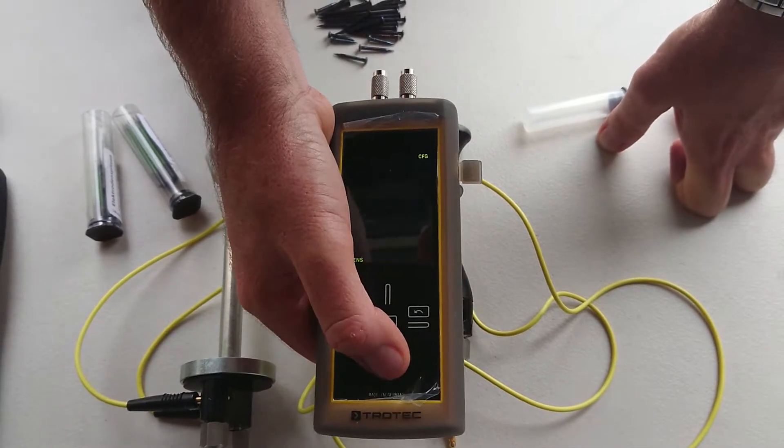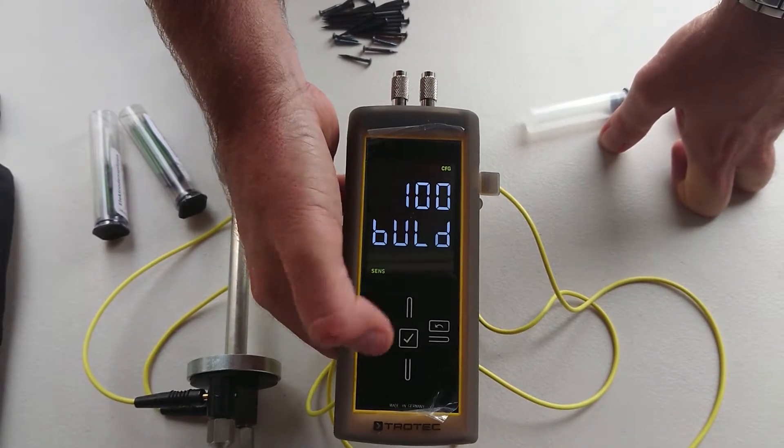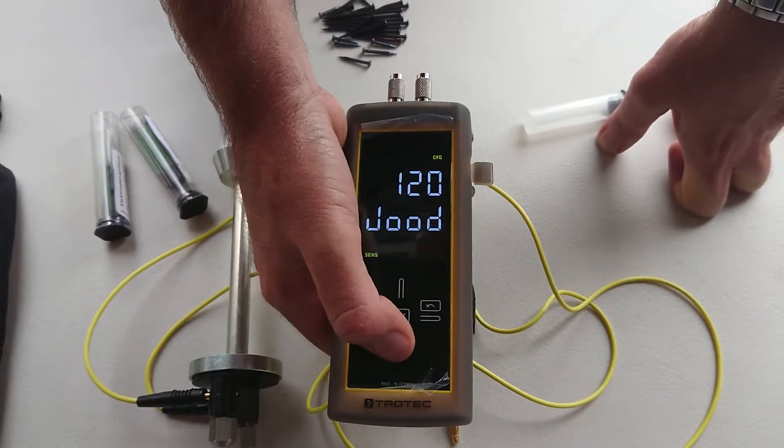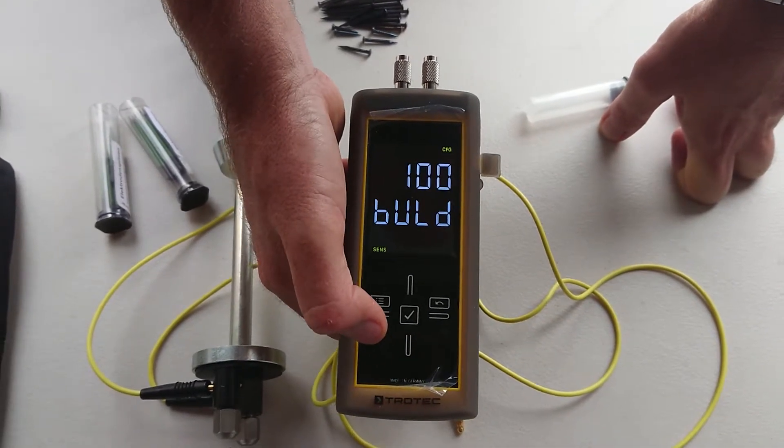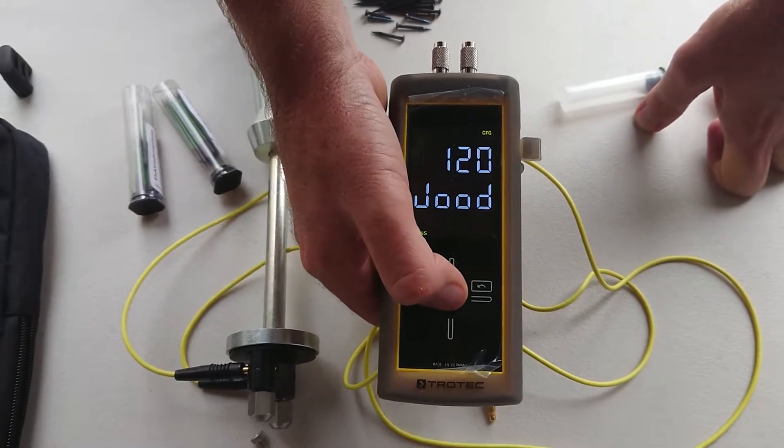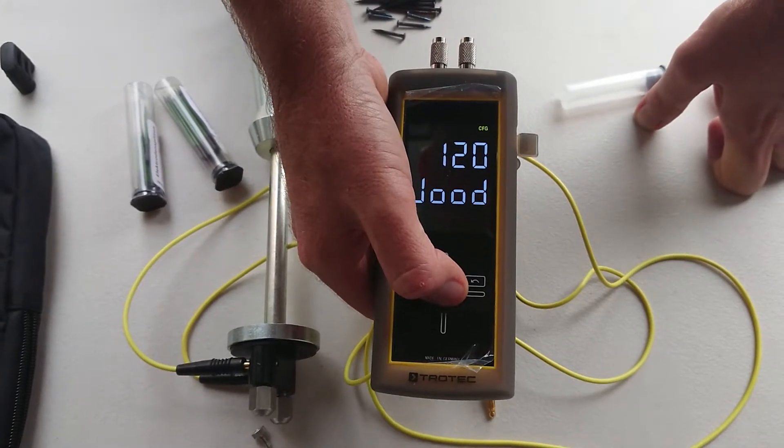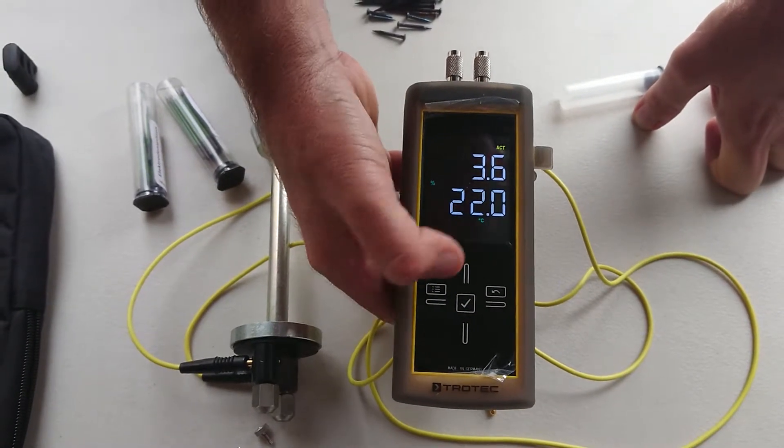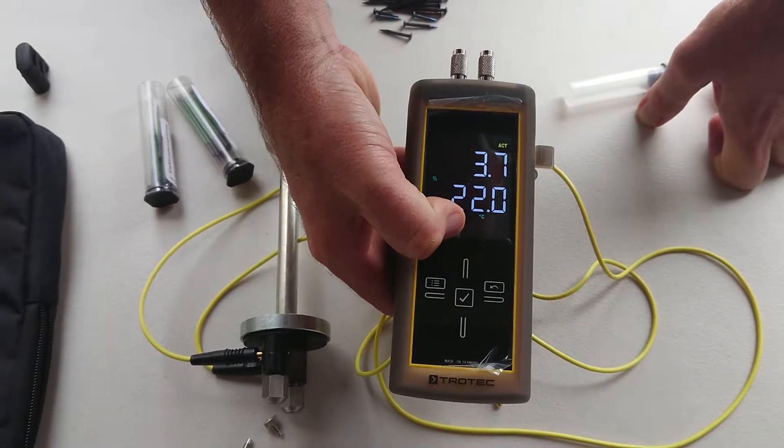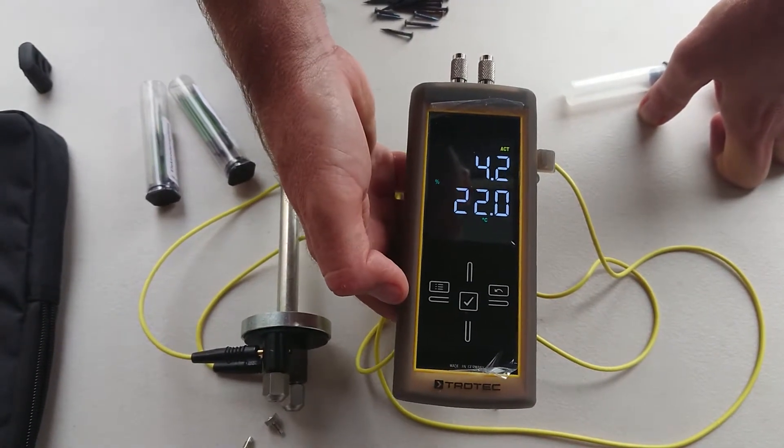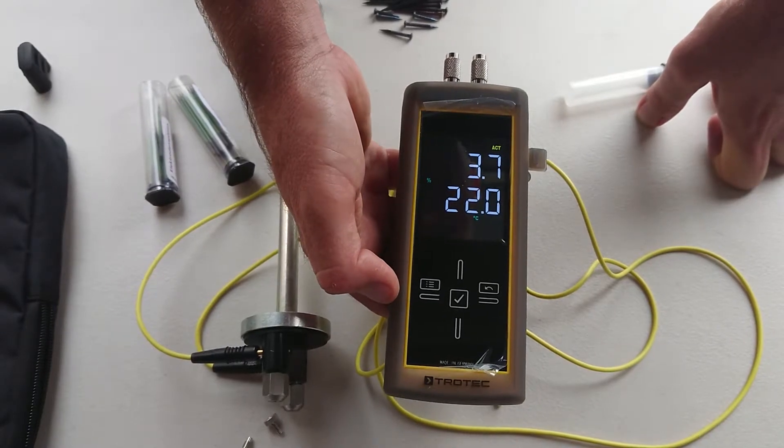Press the tick button and then we can change it between wood and building materials. Wood and building materials. We'll go back to wood. Press the tick button. Now we've got our temperature that we can have in our pin probe as well as our actual percentage in our timber.